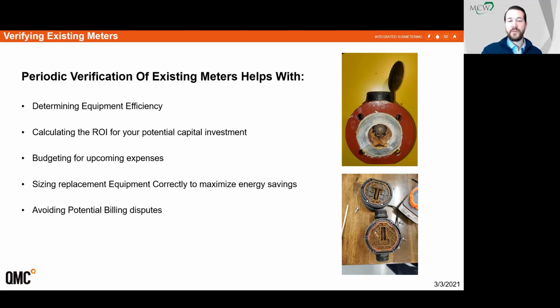Yeah, those are definitely powerful images. I'm just curious, how often should a building operator be completing an internal check of a sub-meter? So it really depends on the utility type and the meters that are deployed for that particular utility. For example, for water, we are trying our best now for more critical and larger loads to move away from meters that have moving parts, because with moving parts, you're highly dependent on your water quality, and if your water is hard and it has calcium in it, you're going to have buildup, and eventually your impellers are going to get stuck or are going to get damaged.